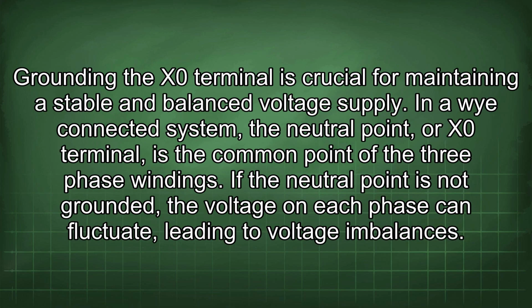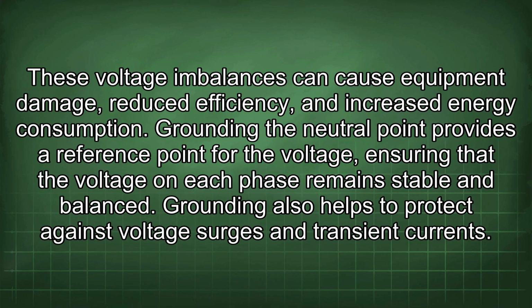Grounding the X0 terminal is crucial for maintaining a stable and balanced voltage supply. In a Y-connected system, the neutral point, or X0 terminal, is the common point of the three-phase windings. If the neutral point is not grounded, the voltage on each phase can fluctuate, leading to voltage imbalances. These voltage imbalances can cause equipment damage, reduced efficiency, and increased energy consumption.